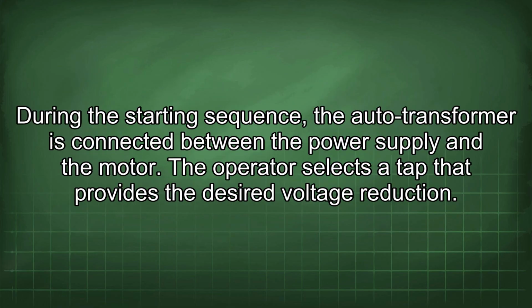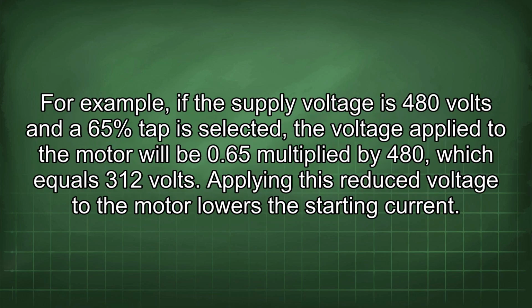During the starting sequence, the auto-transformer is connected between the power supply and the motor. The operator selects a tap that provides the desired voltage reduction. For example, if the supply voltage is 480 volts and a 65% tap is selected, the voltage applied to the motor will be 0.65 multiplied by 480, which equals 312 volts.